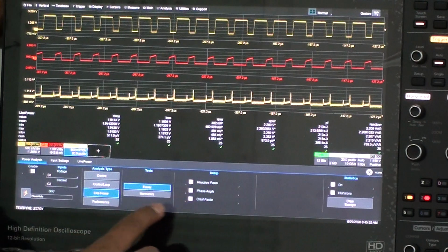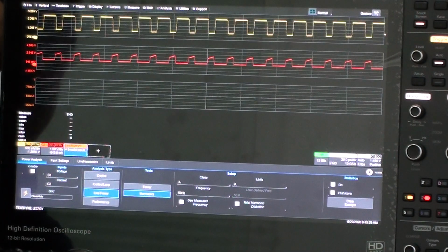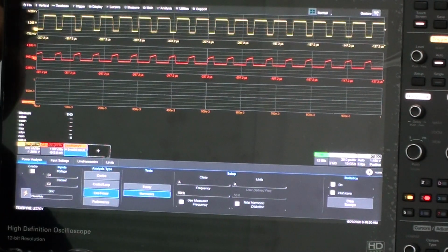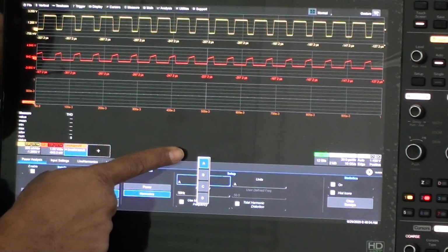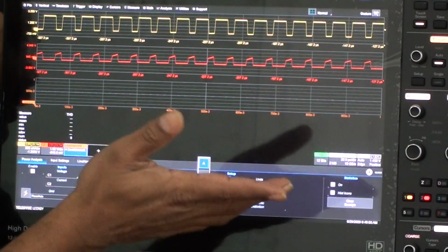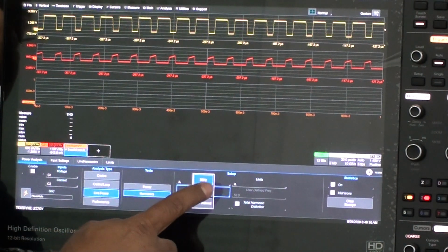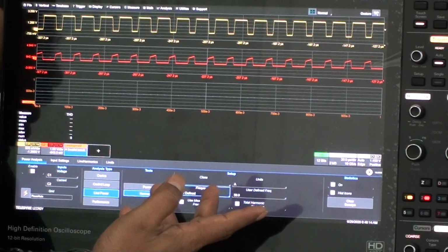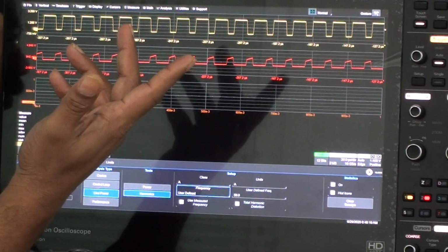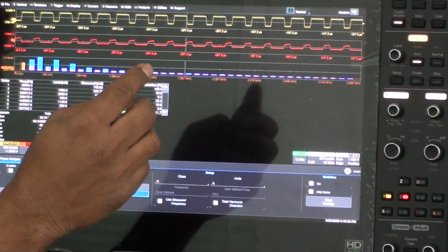You can look at the real power at this, and we are looking at harmonics. Now, you can also take a look at the total harmonic distortion. Here, harmonics again is divided into class A, B, C, and D. This is for the commercial class of power. Either you can use 50 Hertz or 60 Hertz, or user defined. You can use your own sync for power. Right now we are going to use the measured frequency.